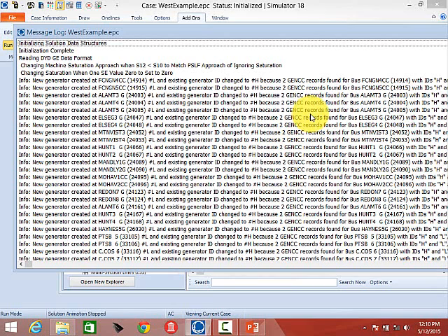Well, and Tom, physically those are usually actually separate units, is that not correct? It's cross-compound? Yes, it's a cross-compound unit. In essence, it's giving you a better model of what's really out there. Power flow has it as one, and Simulator knows it's cross-compound because of GENCC in the dynamics data, and then it's creating another one, which is in fact the true physical case, two separate machines. Right, it's two physical machines. So to do transient stability, we have to treat it as two physical machines. In power flow it's okay, you can combine it, but in transient stability, it's two separate machines.